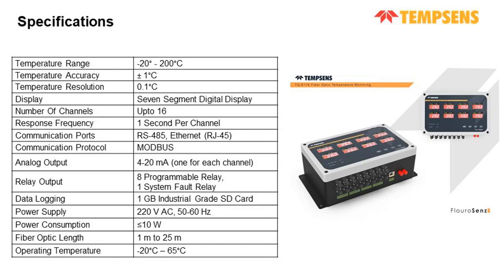So this is the general specification of the product that Tempsens is making. It has a temperature measurement range of -20 degrees centigrade to 200 degrees centigrade, with an accuracy of ±1 degree centigrade and a resolution of 0.1 degree centigrade. The temperature of each channel can be seen on the display provided on the controller itself, which is a 7-segment digital display. The maximum number of supported channels is 16, and the response time of each channel is 1 second per channel.